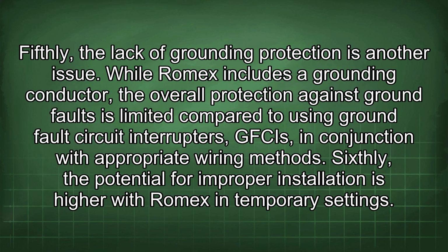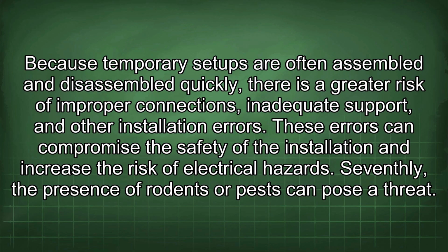Fifthly, the lack of grounding protection is another issue. While Romex includes a grounding conductor, the overall protection against ground faults is limited compared to using ground fault circuit interrupters (GFCIs) in conjunction with appropriate wiring methods. Sixthly, the potential for improper installation is higher with Romex in temporary settings. Because temporary setups are often assembled and disassembled quickly, there is a greater risk of improper connections, inadequate support, and other installation errors. These errors can compromise the safety of the installation and increase the risk of electrical hazards.